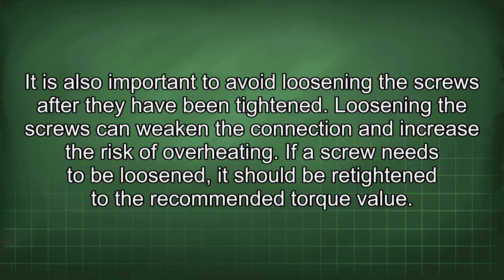It is also important to avoid loosening the screws after they have been tightened. Loosening the screws can weaken the connection and increase the risk of overheating. If a screw needs to be loosened, it should be retightened to the recommended torque value.